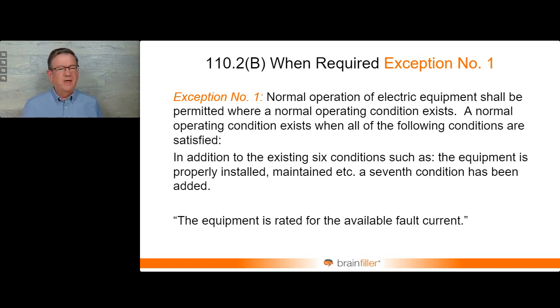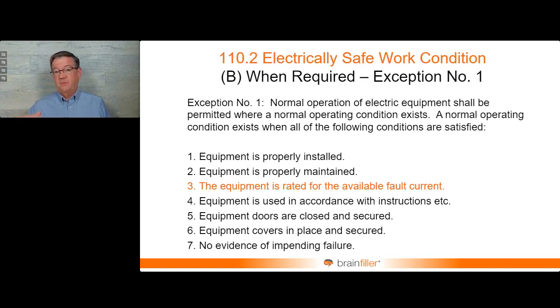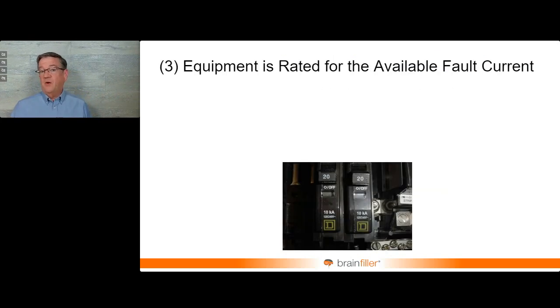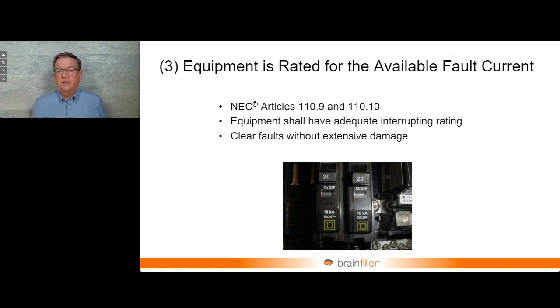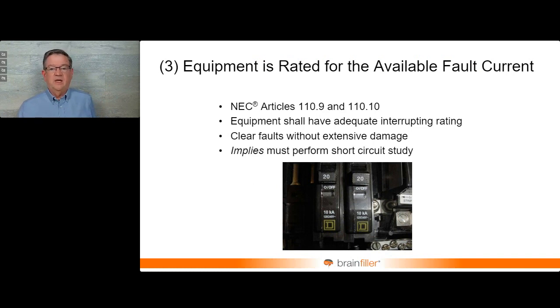Rated for the available fault current. How did that get in there? Well, think about it. You're operating equipment. If something goes wrong, if the equipment's not properly rated for the fault current, that could end badly if a fault occurs. So that was added. It was actually added as the 3rd item. So we still have the original items, and the available fault current got pushed in there at number 3. It's actually a requirement anyway. The National Electrical Code, which is what this is from, Articles 110.9 and 110.10, requires that the equipment is rated for the available fault current. So in NFPA 70E, that is in there as well for normal operation.